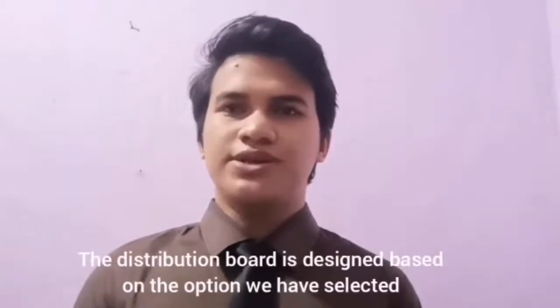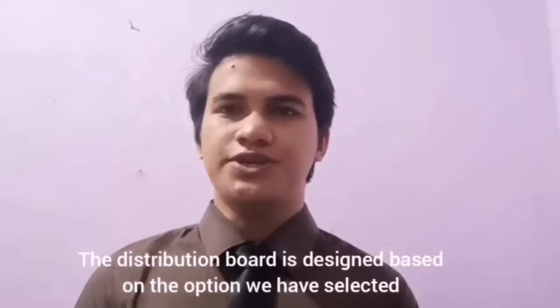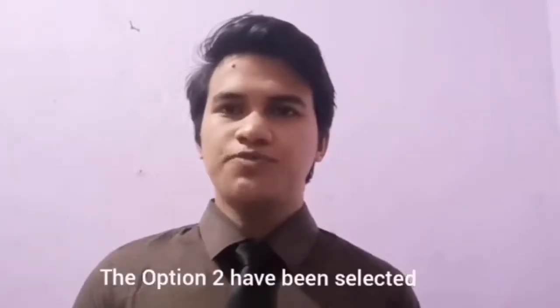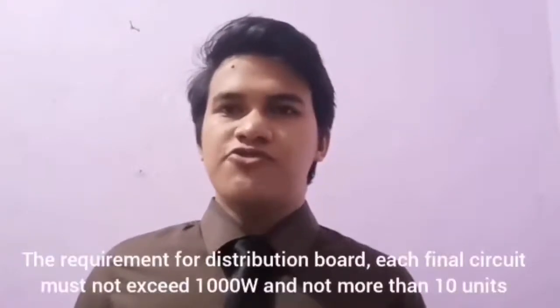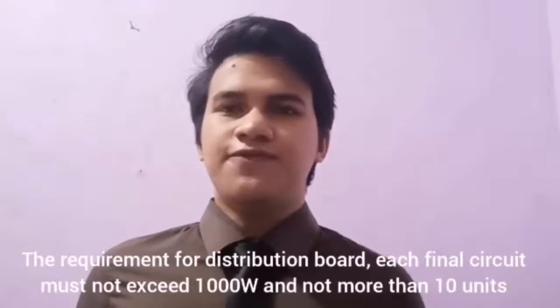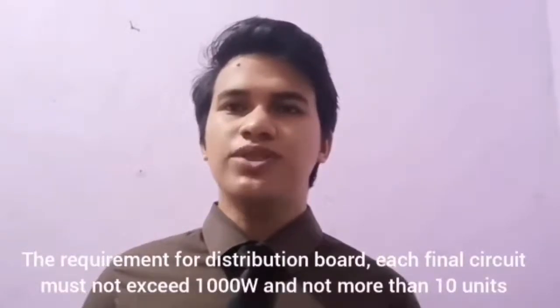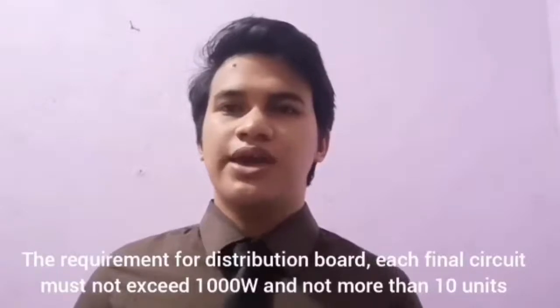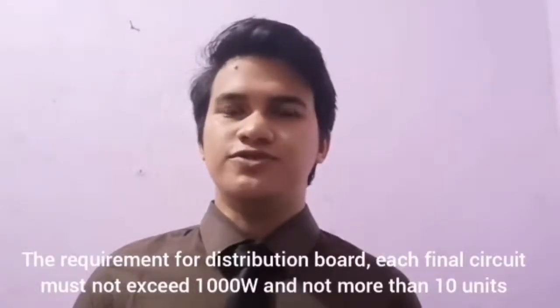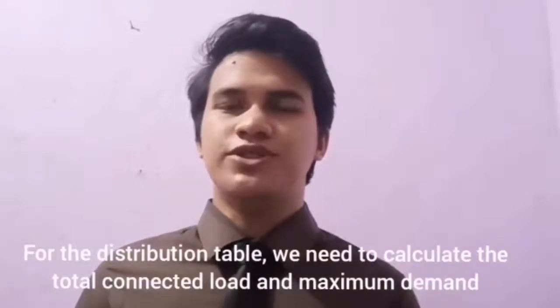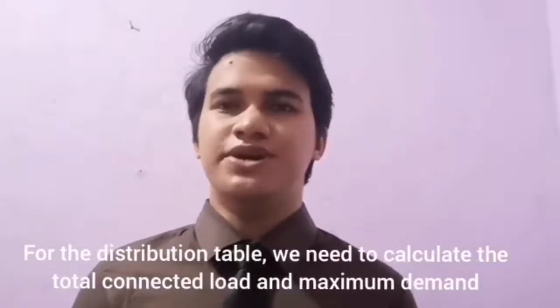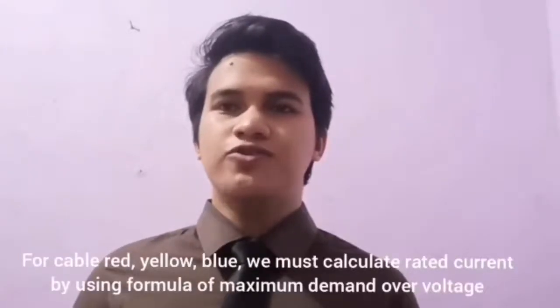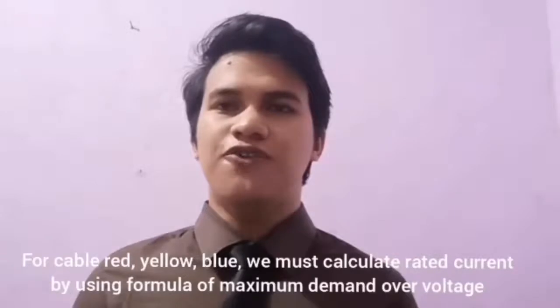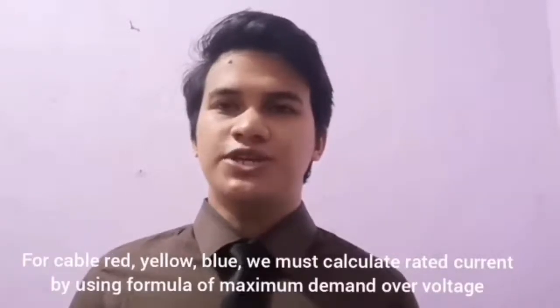The distribution board is designed based on the option that we have selected. Option 2 has been selected. For the requirement of the distribution board, each final circuit must not exceed 1000 watt and not more than 10 units of load. For the distribution board table, we need to calculate the total connected load and maximum demand. For the cable red, yellow, blue, we must calculate the rated current using the formula of maximum demand over voltage.